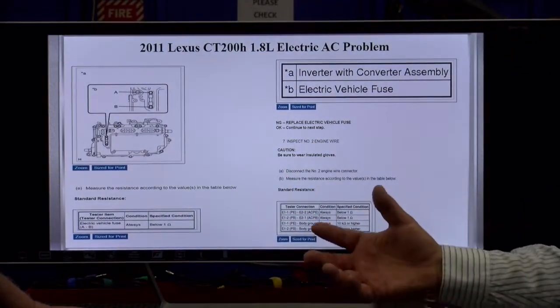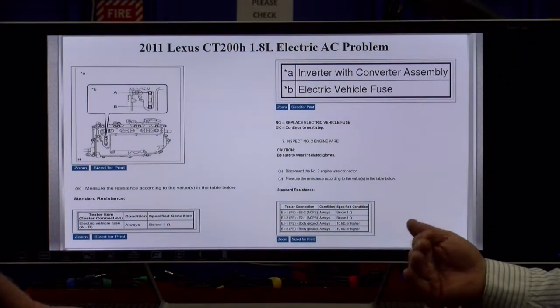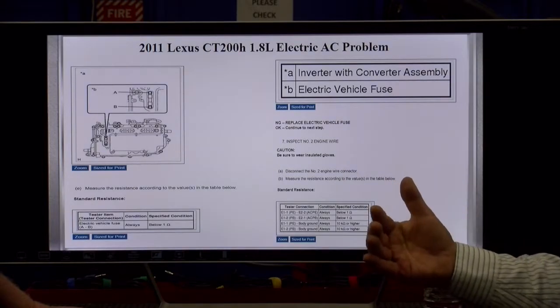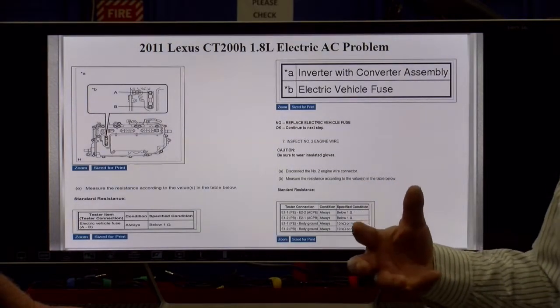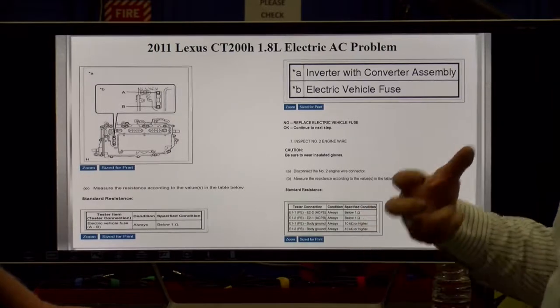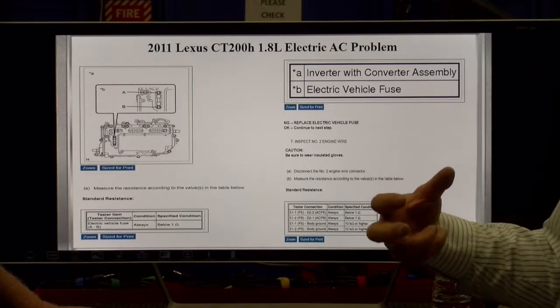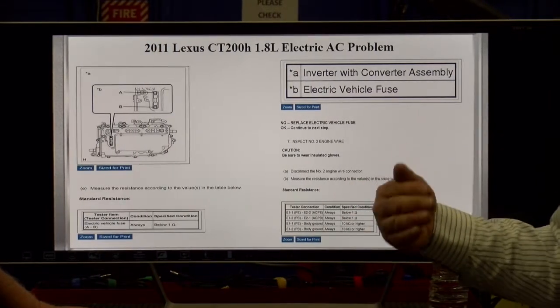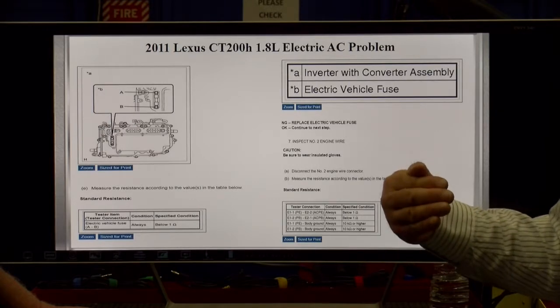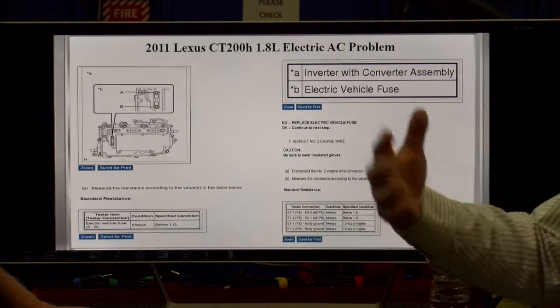Well, the meg ohm meter does resistance, but there's nothing like a real good voltage test. Because the whole idea of a meg ohm meter is to pressurize it, like we would pressurize a pipe. Voltage is pressure, current is flow. We'd want to see if we pressurize it, does it hold or is it leaking somewhere?